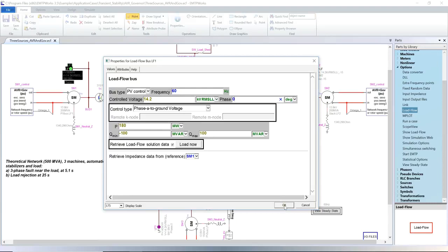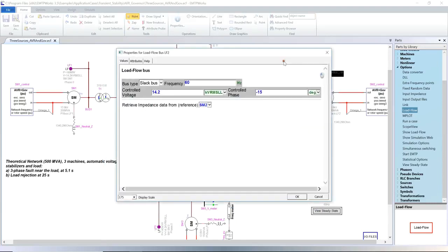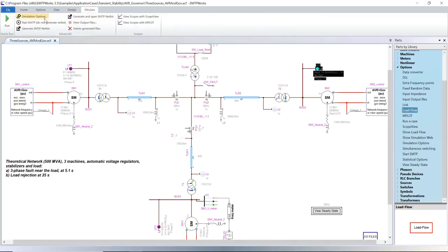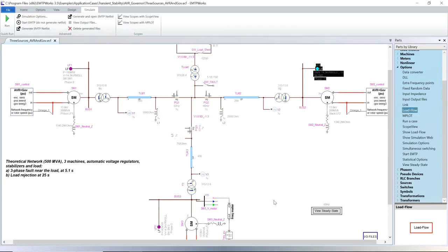For the load flow calculation, one of the machines is set as the slack. After the load flow calculation for the steady state calculation, the machines are represented by Thevenin equivalencies. If start steady state solution from load flow solution is selected in the simulation options, the angle and magnitude of the Thevenin source is automatically adjusted to match the load flow results.